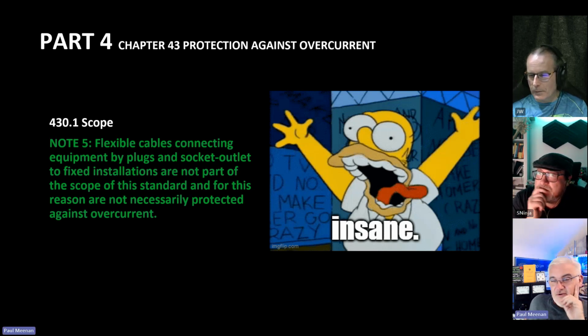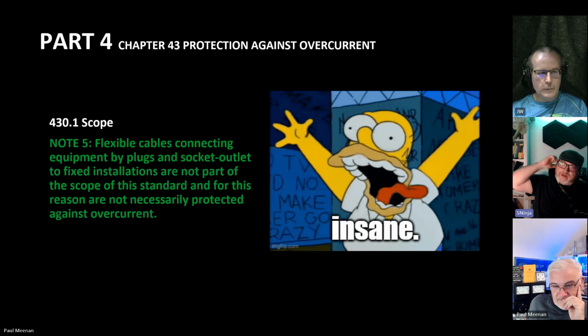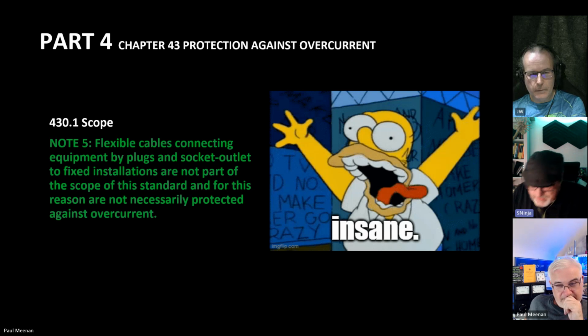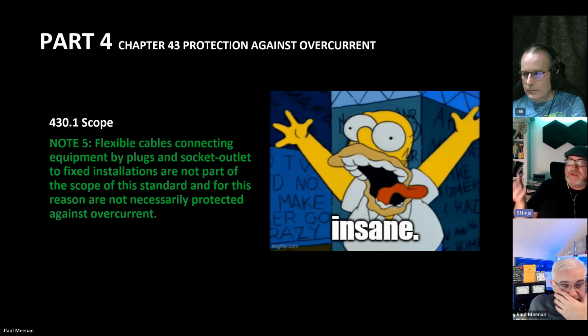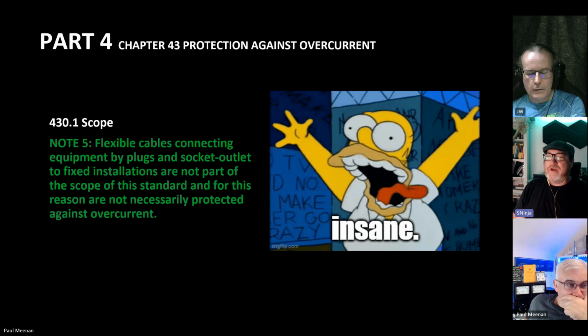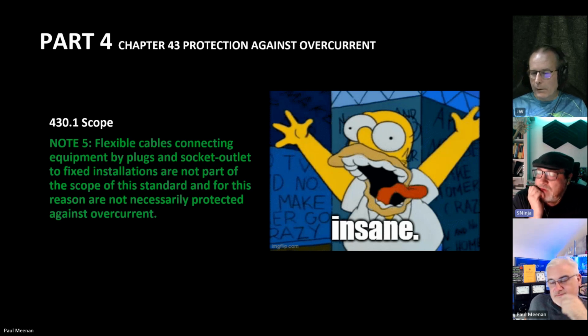I was thinking 7909, something had slipped from maybe there. With 7909 we have 16 amp, 32 amp, 63 amp, but we just make sure the conductors are sized to that overcurrent protected device. We have the MCBs, so we still have overcurrent protection in there. Any time we split it down, for example a 32 amp split down to a 16 amp on a 32 amp feed, it's non-compliant. You have to have overcurrent protection throughout the system.